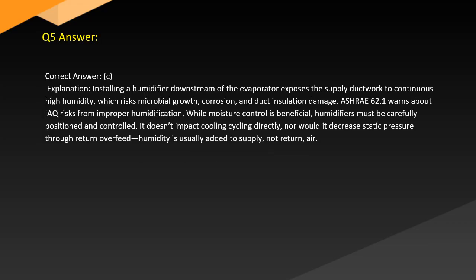Answer. Correct answer: C. Explanation. Installing a humidifier downstream of the evaporator exposes the supply ductwork to continuous high humidity, which risks microbial growth, corrosion, and duct insulation damage. ASHRAE 62.1 warns about IAQ risks from improper humidification. While moisture control is beneficial, humidifiers must be carefully positioned and controlled. It doesn't impact cooling cycling directly, nor would it decrease static pressure through return overfeed. Humidity is usually added to supply, not return air.